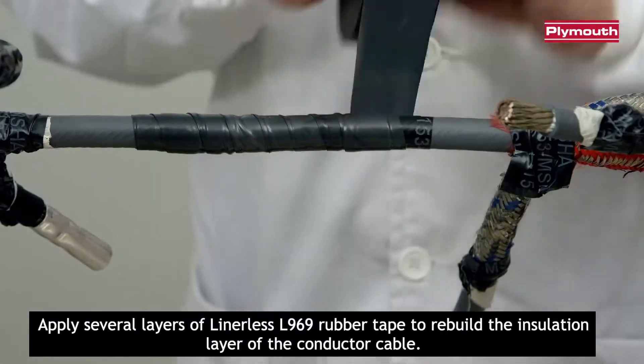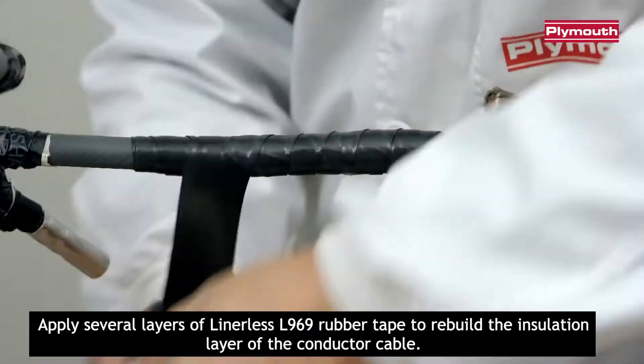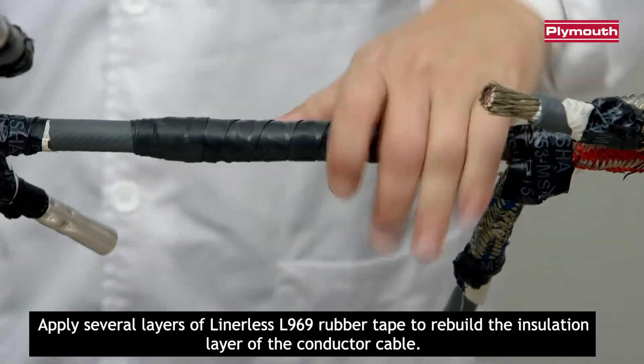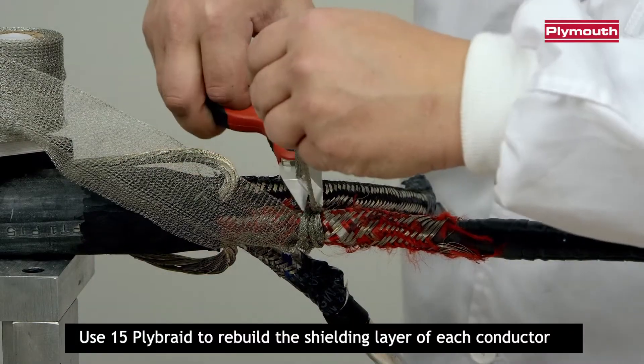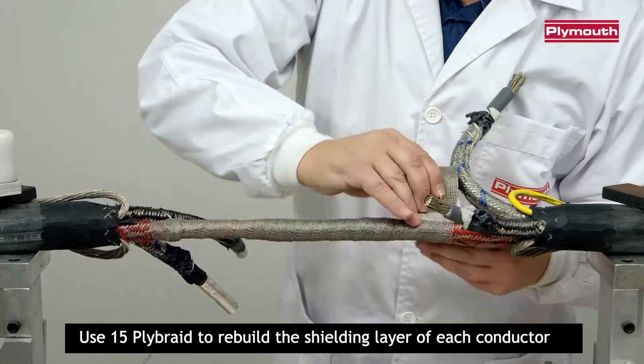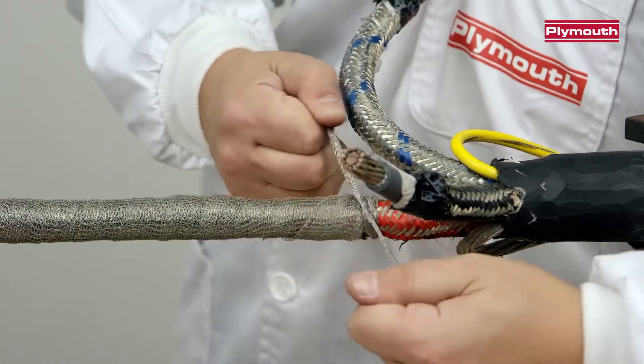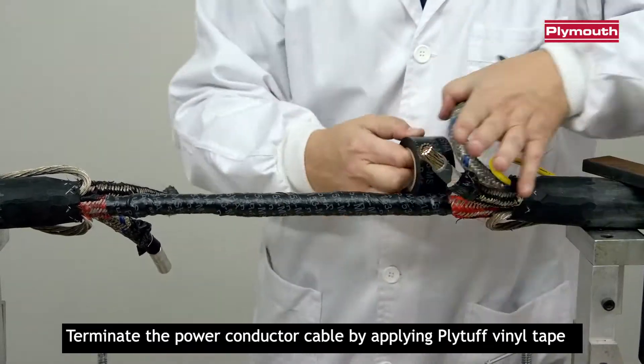Apply several layers of linerless L969 rubber tape to rebuild the insulation layer of the conductor cable. Use 15 Ply Braid to rebuild the shielding layer of each conductor. Terminate the power conductor cable by applying Plytuff Vinyl Tape.